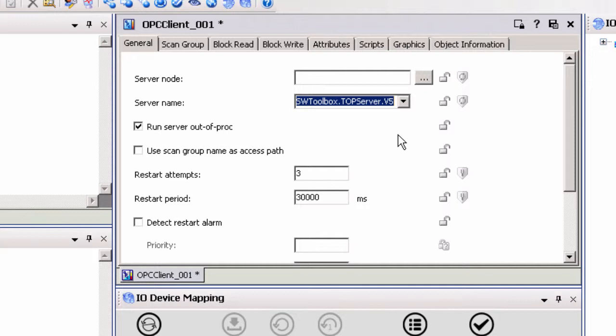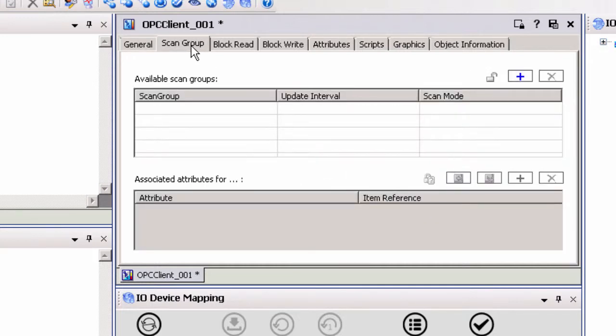If you experience problems browsing for OPC servers, please see our DCOM tutorial guide. Now that TopServer is selected, navigate to the scan group tab of the OPC client object. System Platform requires that at least one scan group is configured. If all items require the same update interval, you will only need to enter one scan group. If your items require multiple update intervals, you would configure multiple scan groups, each with its own update interval.